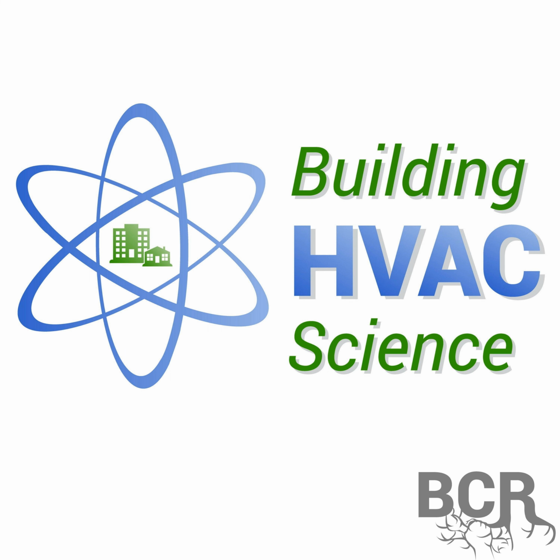If the source of heat is combustion, natural gas, oil, or propane, the BTUs per hour comes from the BTU input times the steady state efficiency. Now, the steady state efficiency is a number you have to take from your combustion analyzer. So if you want to make a good measurement, you actually have to take some other background measurements in order to add up to a good measurement for your airflow. If a combustion analyzer is not available, the manufacturer's literature could be used to determine the output BTUs of the furnace, provided the manifold pressure is correct, and the orifices are designed for the heat content of the BTUs of the fuel used, or consistent with the design input of the furnace.